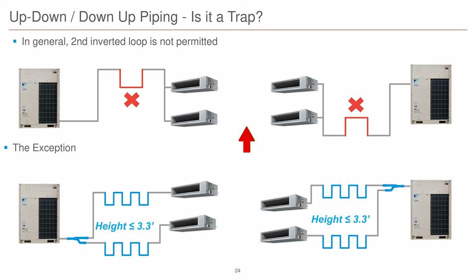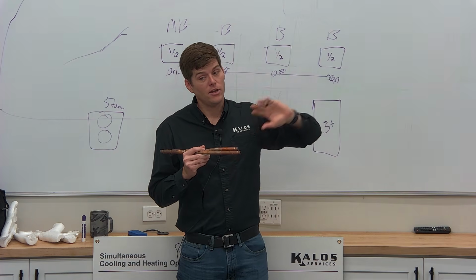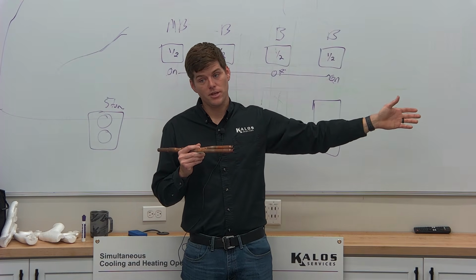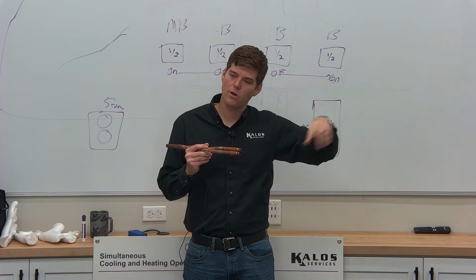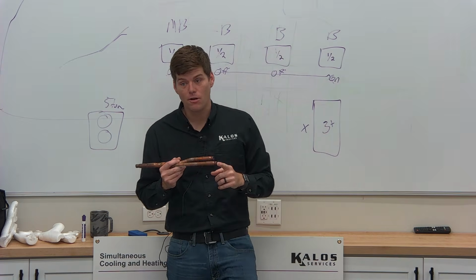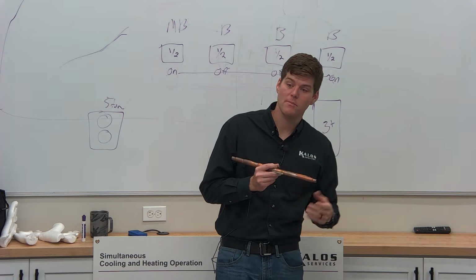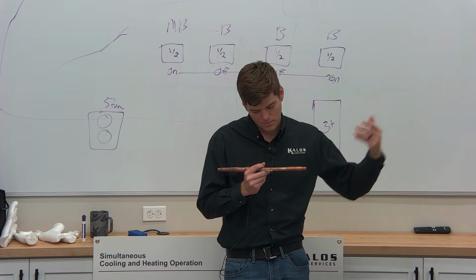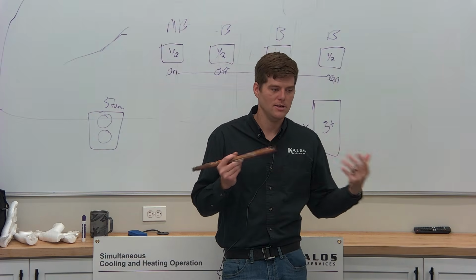So that's traps on the main line. You notice the second picture down below is not traps on the main line. This is actually after a Refnet. So when you leave a Refnet, you actually have that 3.3 foot variation. So you can go up and down, spell your name in the ceiling, because you like to leave a mark, you like to make a statement. I don't judge. Right? And then it goes to the fan coil, that's not an issue. It can overcome that because there's refrigerant that's going to be flowing through that. But when you do it on the main line itself that supplies all the other indoor units, the amount of oil that's being commuted down that line to the outdoor unit is in a larger quantity.